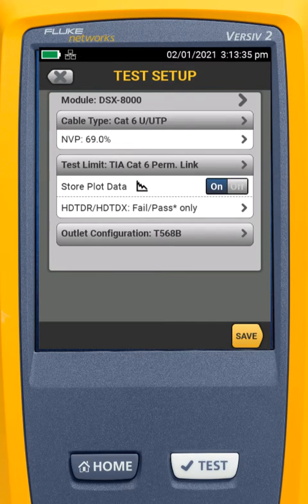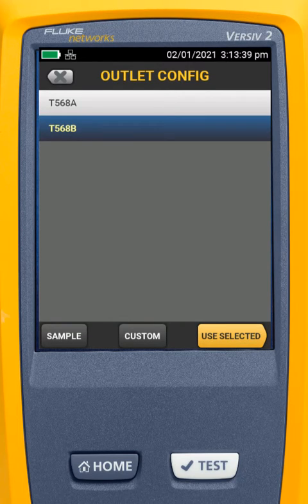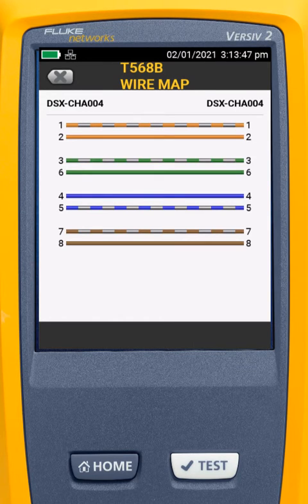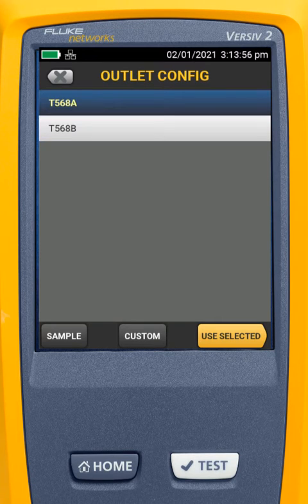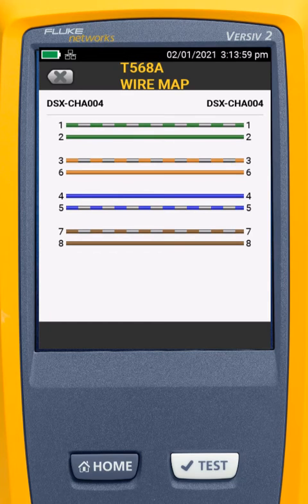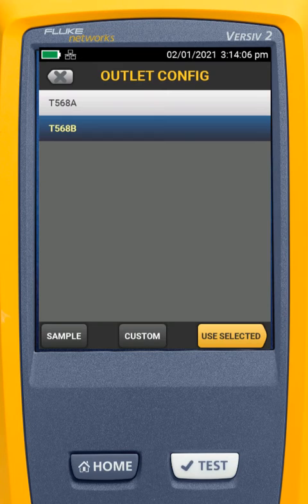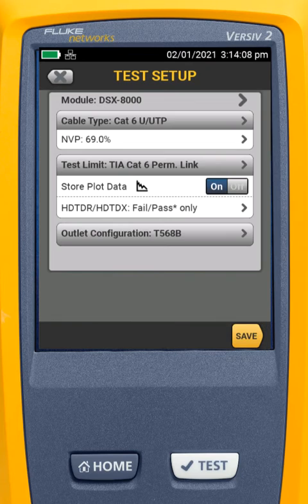Lastly, we're going to choose our outlet configuration. Here we have 568A or 568B. This will determine which pairs the orange and the green conductors are on. In this case, orange is on 1 and 2, and green is on 3 and 6. If we selected 568A, green would be on 1 and 2, and orange would be on 3 and 6. This is mostly for documentation purposes — it doesn't really change the outcome of the test. Today we're going to use 568B, and I'll say Use Selected.